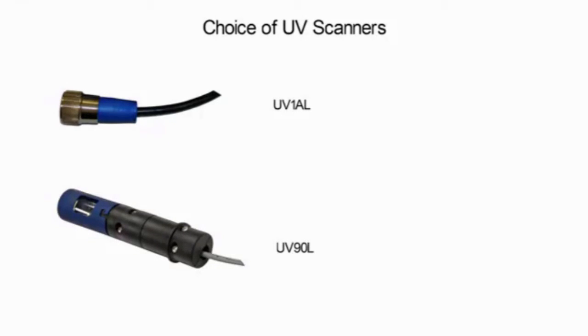The UV-1AL and UV-90L ultraviolet flame scanners are non-self-checking and should be applied only to burners that cycle a minimum of once per 24 hours.